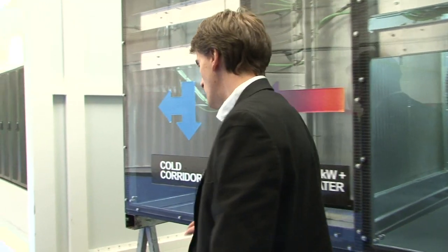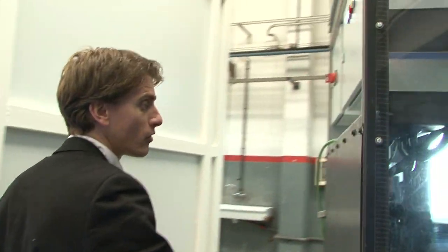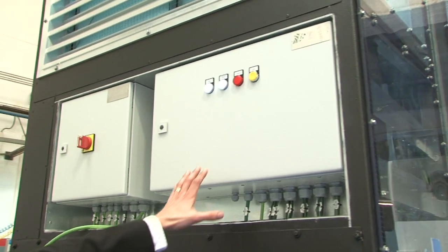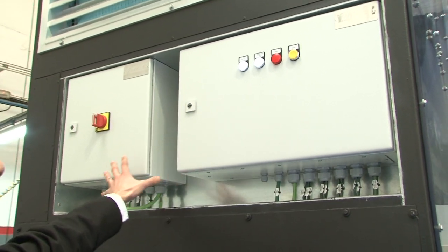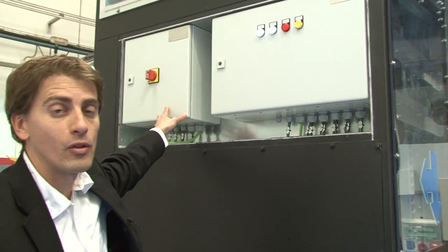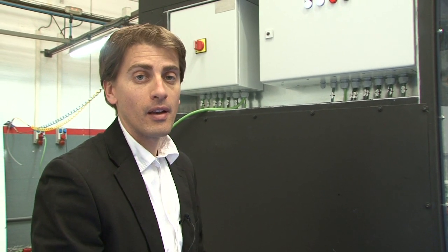All these units are totally independent of one another, so redundancy is embedded in the modules, and therefore we are providing an independent CPU on the unit, as well as a totally independent electrical switchboard, in order to provide the redundancy per module and not as a whole system.